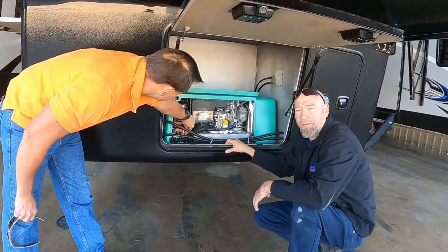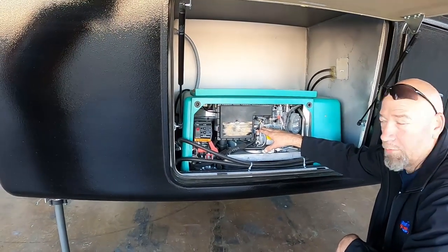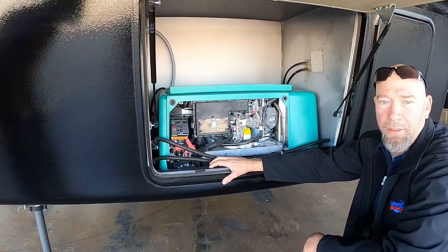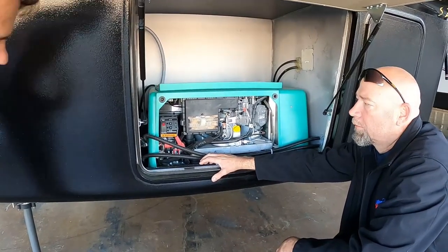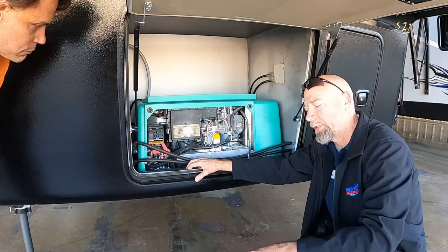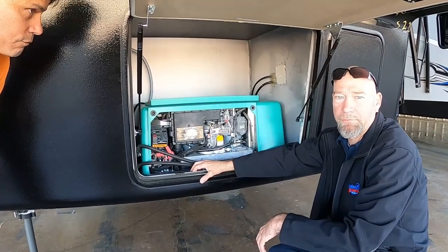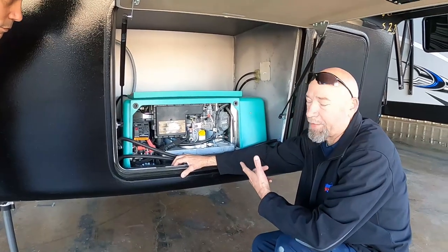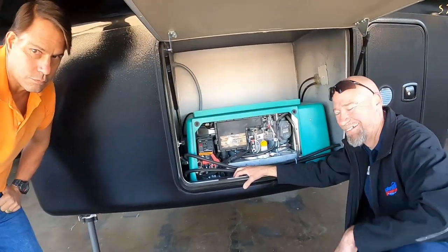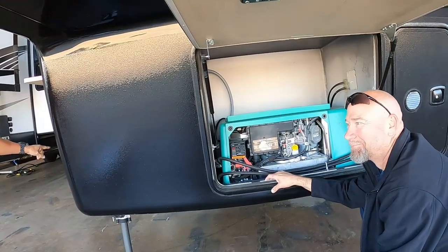The generator is gas. The two fuel tanks are right next to each other - you don't fill the generator here separately. Now for maintenance: you fill the oil right here, there's a pickup with a hose. To drain it, put a little bucket here and open it up. It has an automotive oil filter that screws in at the bottom - easy to do. Use 15W-40 oil, though it depends on elevation. Change the air filter every 450 hours, change the oil every 150 hours.